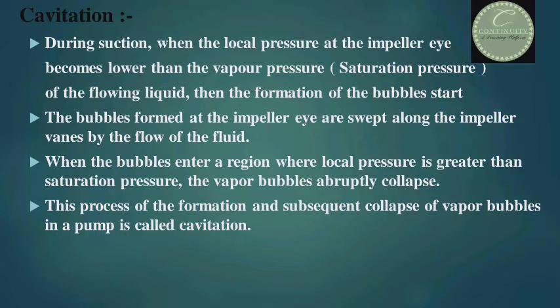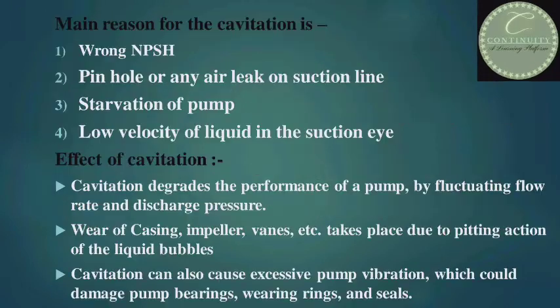The bubbles formed at the impeller eye are swept along the impeller vanes with the flow of the fluid. When the bubbles enter a region where local pressure is greater than the saturation pressure, the vapor bubbles abruptly collapse. This process of the formation and subsequent collapse of vapor bubbles in a pump is called cavitation.